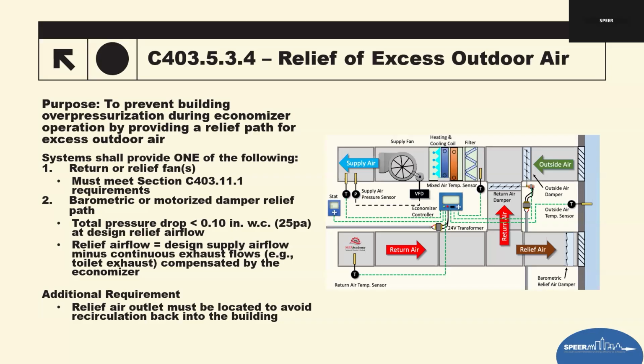Option 2, a barometric or motorized damper relief. So the second option allows either one of those. The key conditions are the relief path must have a very low pressure drop, less than 0.10 inches of water column. Basically, that again goes back to commissioning and making sure that that's meeting those levels. This ensures the system can relieve pressure without adding unnecessary fan energy.